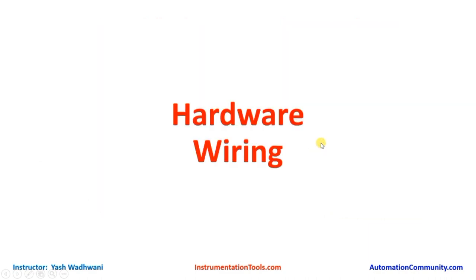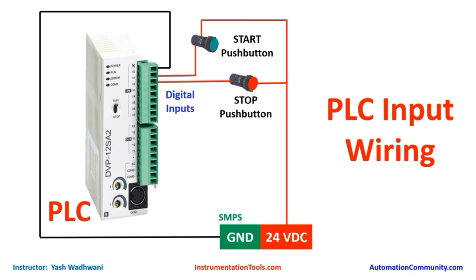Now let us understand the hardware wiring. We have only two inputs — start and stop — since the counter value will be taken from the HMI. In the source-sink configuration, we connect the ground of the SMPS to the common of digital inputs, then connect 24V supply to one terminal of each start and stop button. The other terminal of the start button connects to X0, and the stop button to X1.